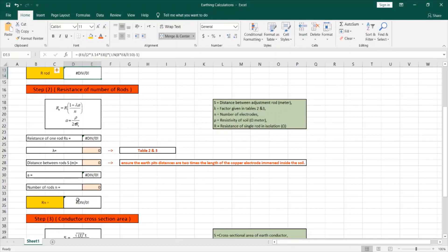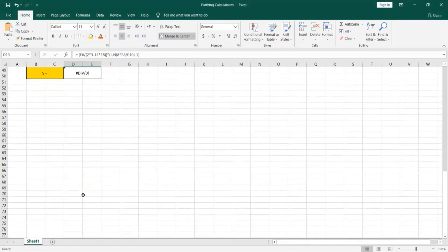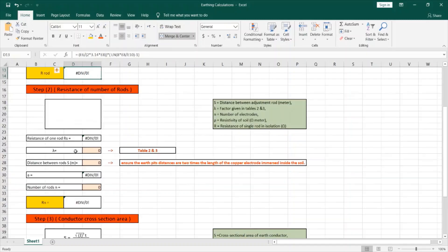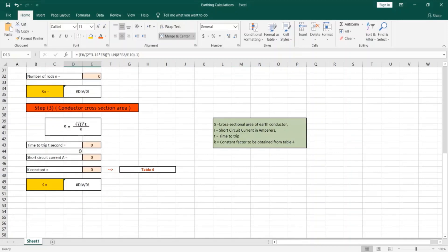At this step we will use the trial and error method to achieve the target resistance. The third step is for calculating the conductor cross-sectional area, or the size of the earthing conductor. We have two methods: either using this formula, which is more accurate, or using a table to determine the size of the conductor in relationship with the size of the phase conductor.